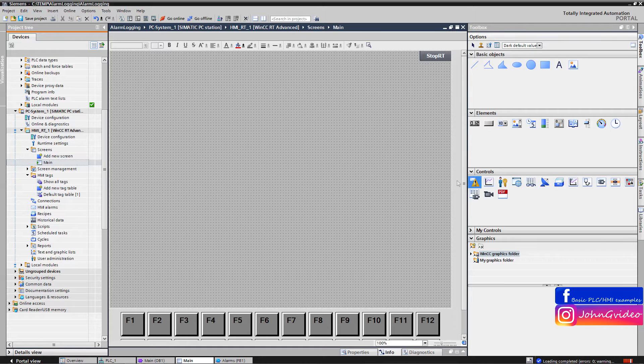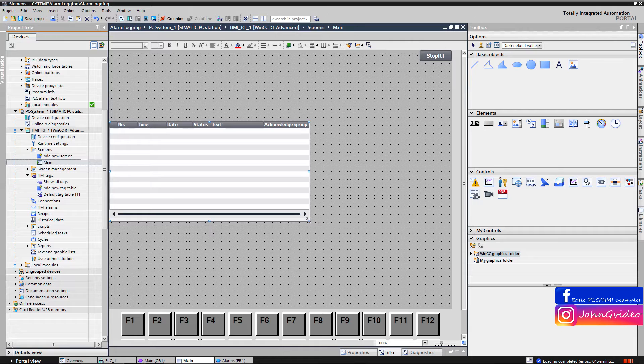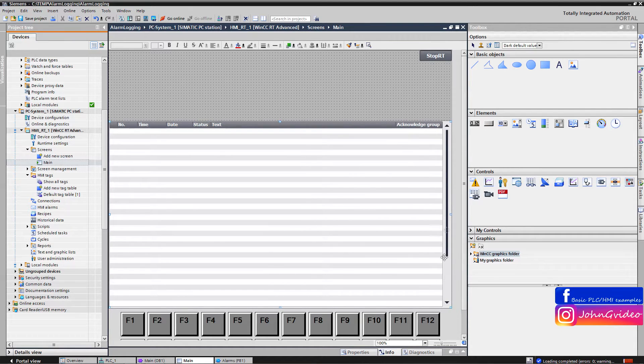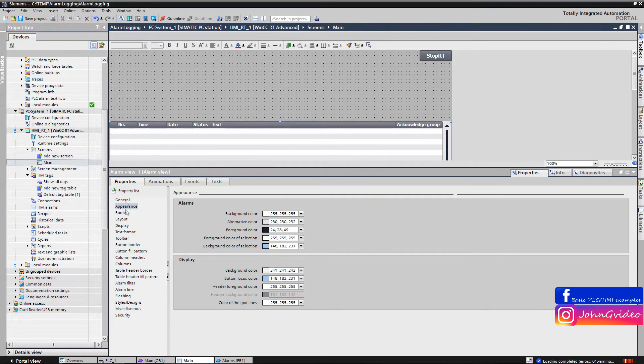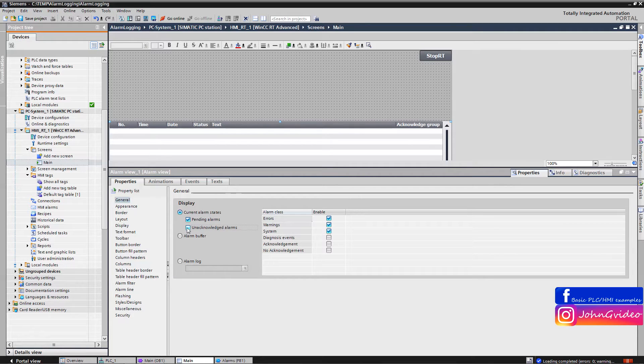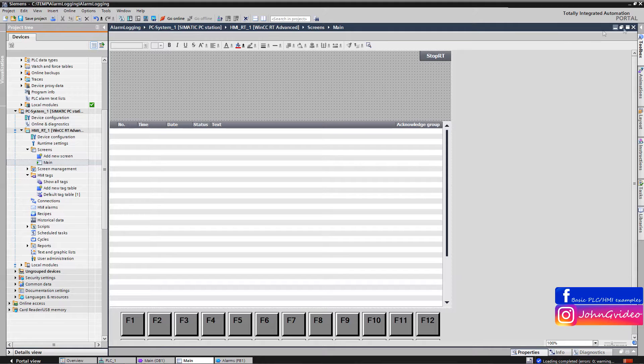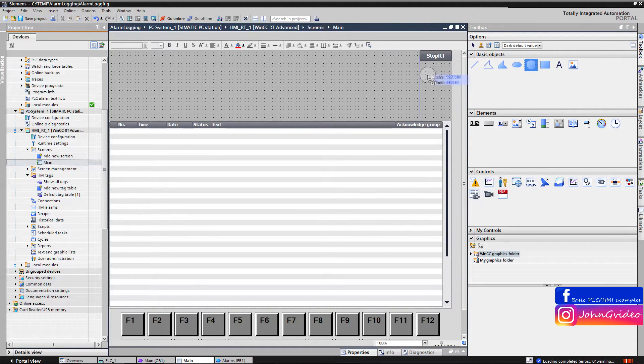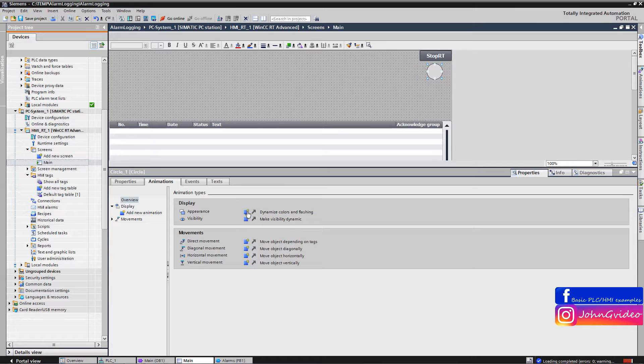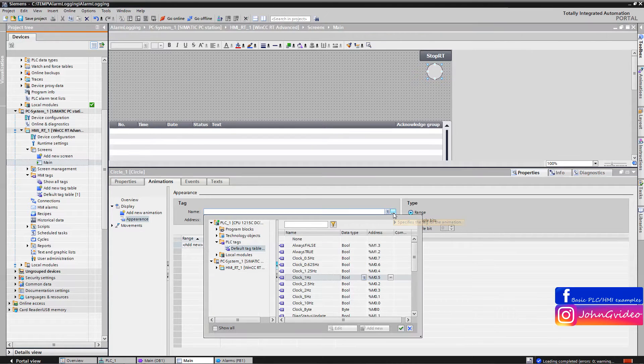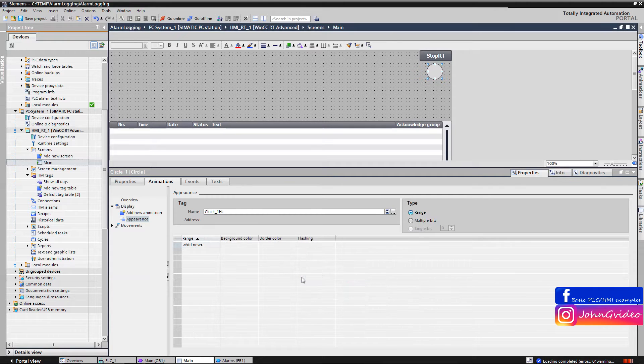First we insert an alarm view to see the state of the alarms on the runtime, and we use it to show only pending alarms. This is why we uncheck the unacknowledged alarms in the display options of the alarm view. We also insert a cycle object, which indicates if we have communication between the PLC and our WinCC Runtime application. If the communication is OK, this object will blink green.